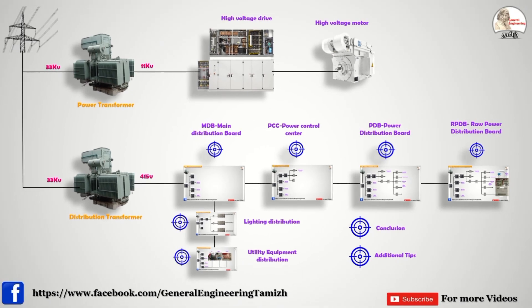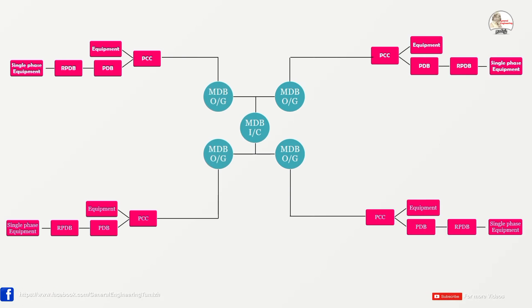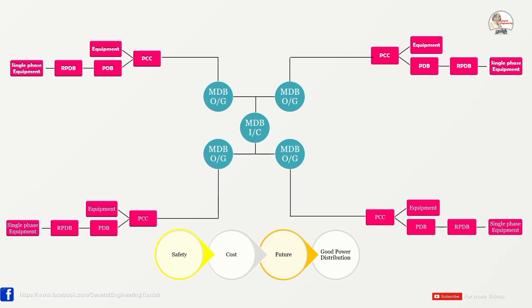Now some additional tips about power distribution. First, choose the proper location for the transformer and MDB. If your plant covers about a two-kilometer radius, the MDB and transformer should be in the middle of the plant. This ensures proper power distribution with minimal transmission loss. If the transformer and MDB are at one end, the cable length increases, increasing transmission losses.